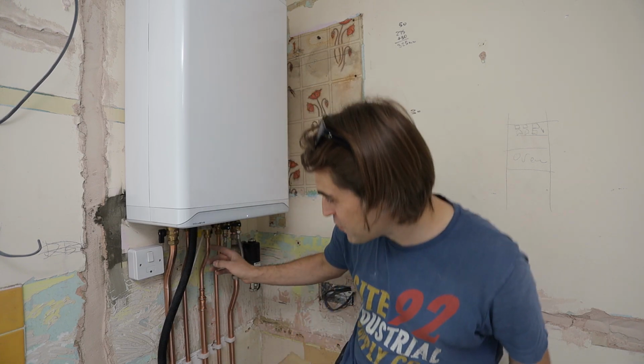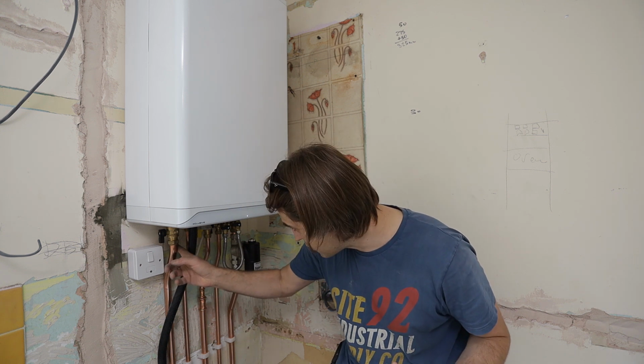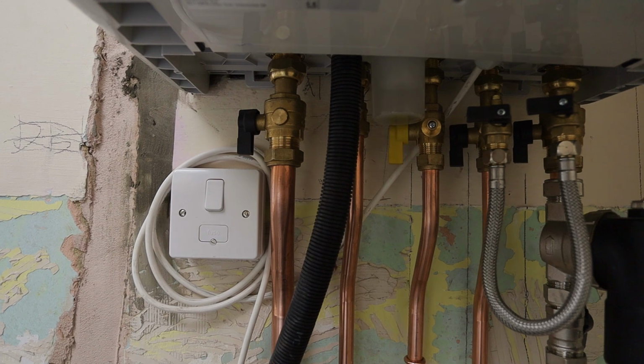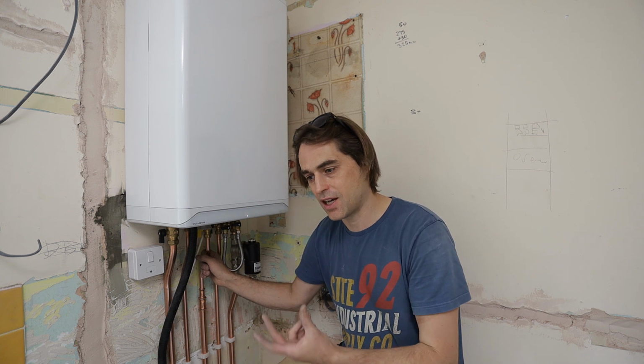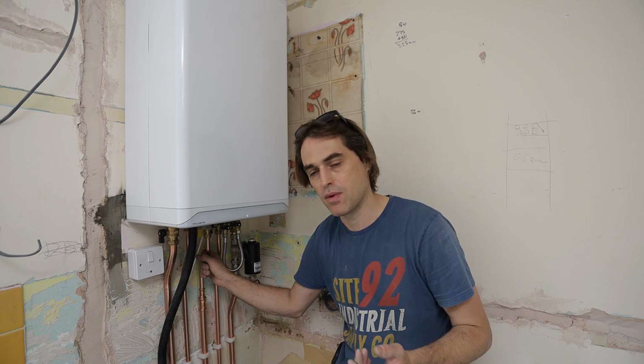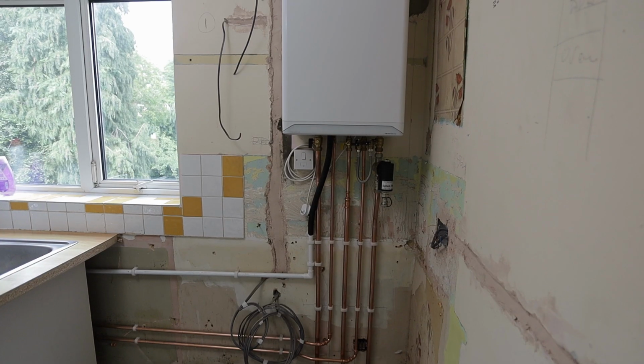You still have to do offsets, and the thing about offsets is every single pipe has a different offset. Flow and return has one size offset, cold and hot are closer to the wall, and then gas is again a different distance, so you have to bend 3 different size offsets on this boiler. On the HRE there was just one offset, 35mm if I remember correctly. On this one every single pipe is different.